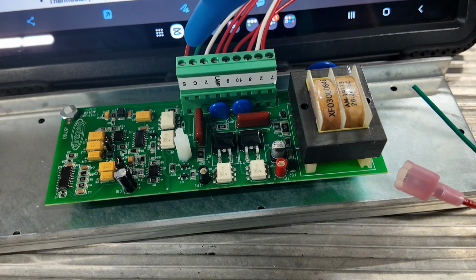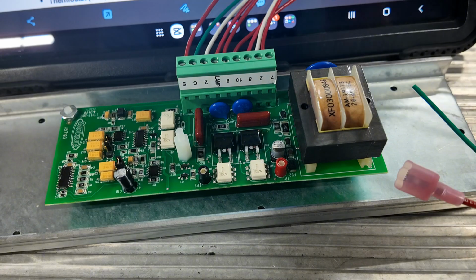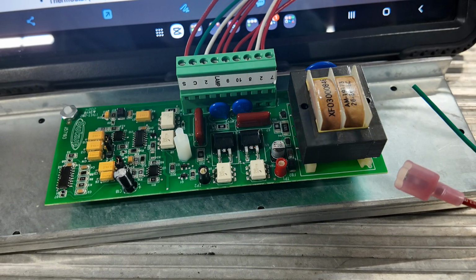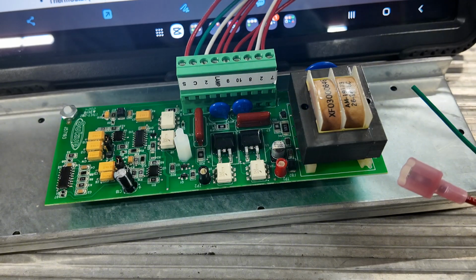Now, there are burners, depending on the burner design, you can add 2 flame sensors to get it so it senses flame better. Now, I have done that. Depending on the burner style, you can get too much flame sensing if you have 2 or 3 flame sensors, and then it can shut off saying we're shorted out.